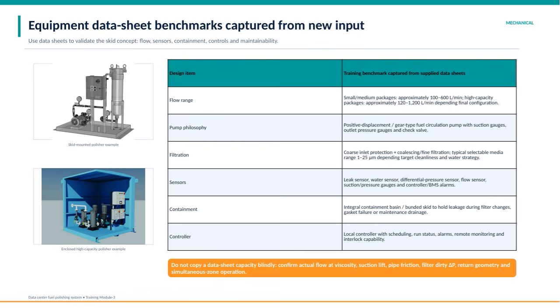When reviewing the design items, the flow range varies from about 100 to 600 liters per minute for smaller or medium packages, and up to 1,200 liters per minute for high-capacity packages, depending on the final setup. The pump philosophy typically involves a positive displacement, gear-type fuel circulation pump equipped with suction and outlet pressure gauges, plus a check valve for reliability.